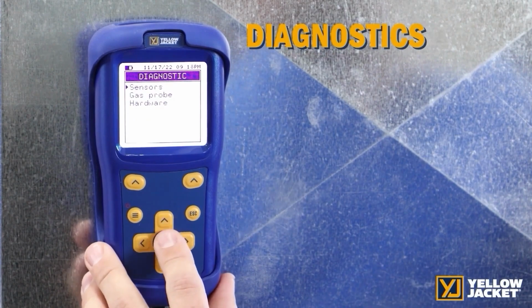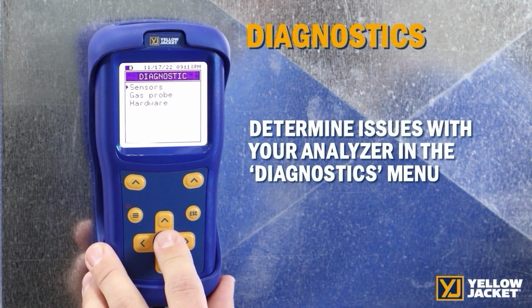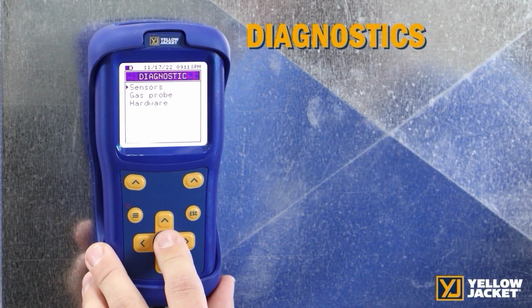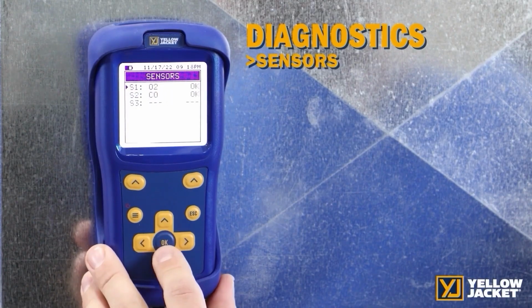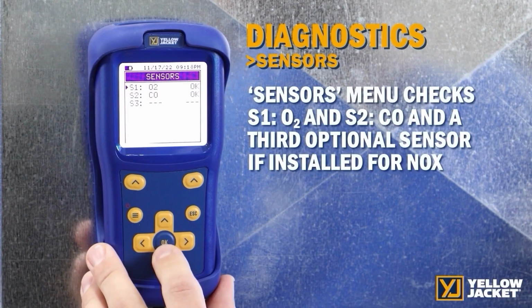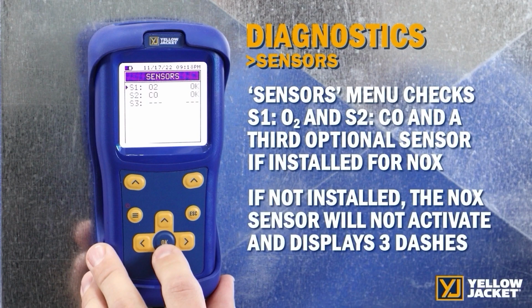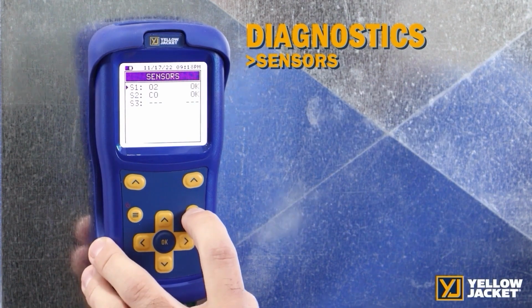The Diagnostics menu is used to determine if there is an issue with your combustion analyzer. The Sensor menu checks the 2 onboard S1: O2 and S2: CO sensors, and a third optional sensor if installed for nitric oxide. If the S3 NOx is not installed, the additional feature will not be activated, and it will be displayed as 3 dashes for the sensor as well as 3 dashes for the sensor performance.